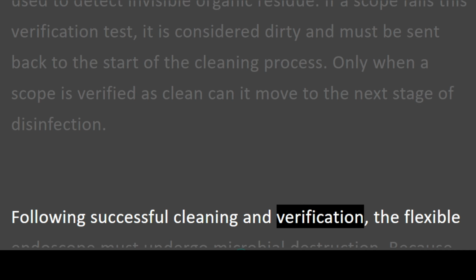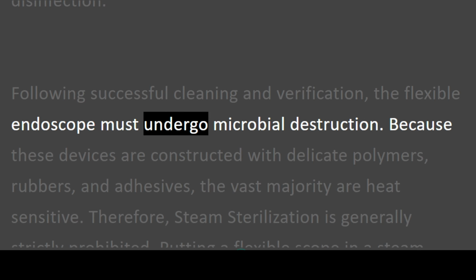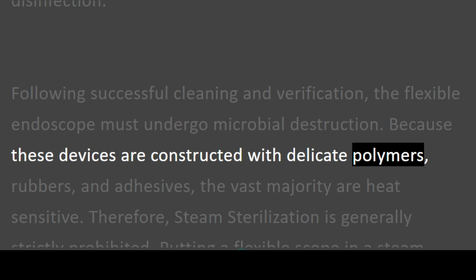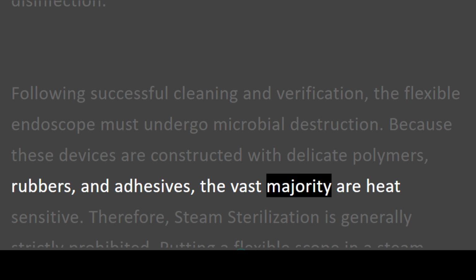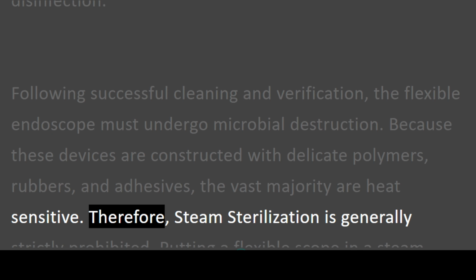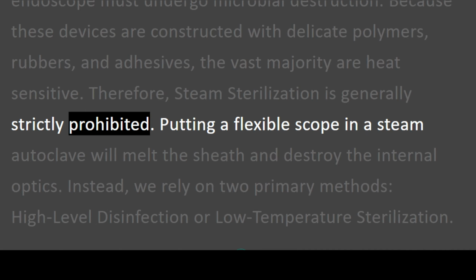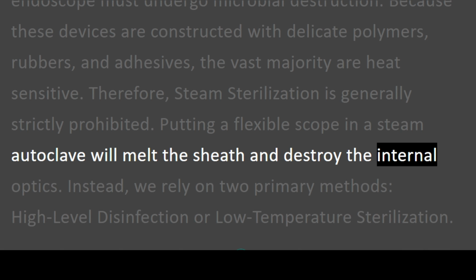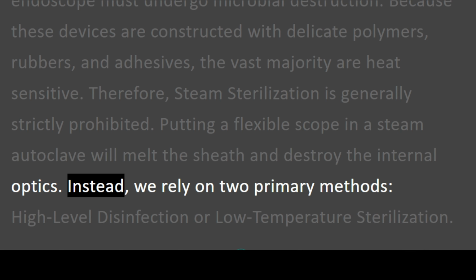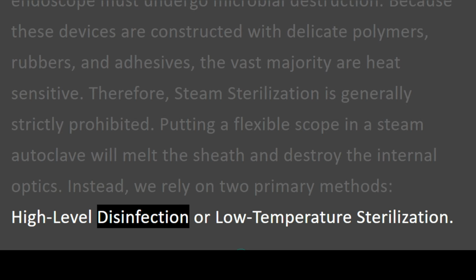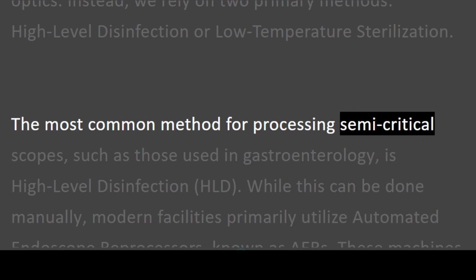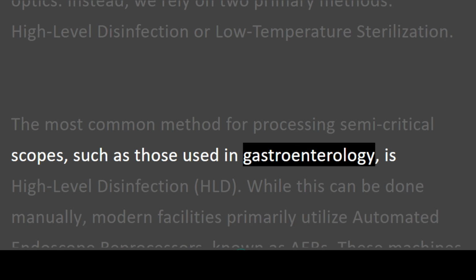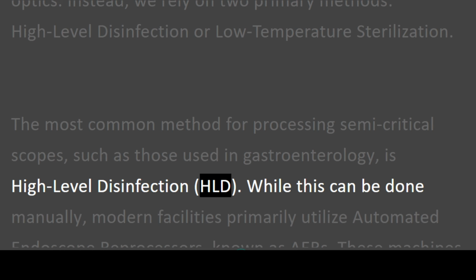Following successful cleaning and verification, the flexible endoscope must undergo microbial destruction. Because these devices are constructed with delicate polymers, rubbers, and adhesives, the vast majority are heat sensitive. Therefore, steam sterilization is generally strictly prohibited. Putting a flexible scope in a steam autoclave will melt the sheath and destroy the internal optics. Instead, we rely on two primary methods: high-level disinfection or low-temperature sterilization. The most common method for processing semi-critical scopes, such as those used in gastroenterology, is high-level disinfection, HLD.